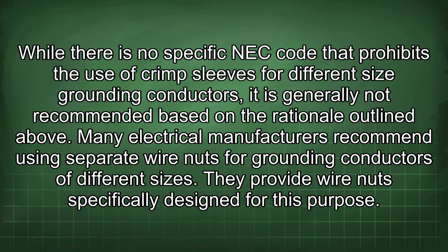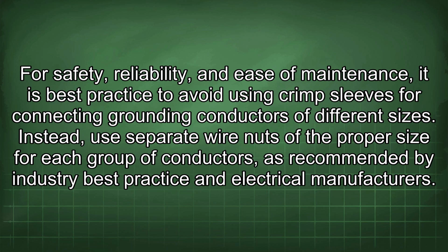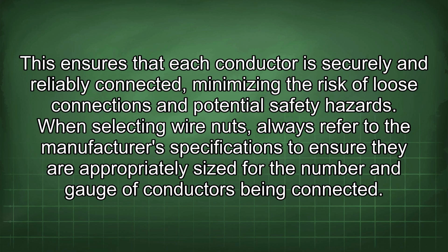Many electrical manufacturers recommend using separate wire nuts for grounding conductors of different sizes. They provide wire nuts specifically designed for this purpose. For safety, reliability, and ease of maintenance, it is best practice to avoid using crimp sleeves for connecting grounding conductors of different sizes. Instead, use separate wire nuts of the proper size for each group of conductors, as recommended by industry best practice and electrical manufacturers. This ensures that each conductor is securely and reliably connected, minimizing the risk of loose connections and potential safety hazard.